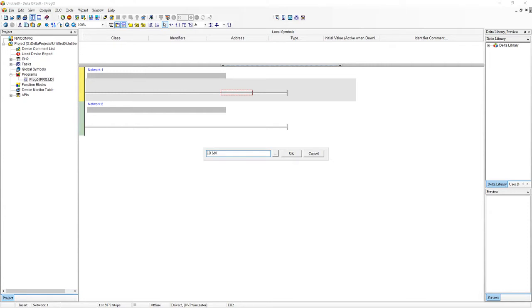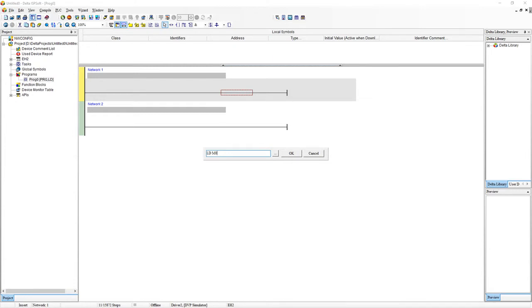So LD is just basically a function which allows us to get an input and when it is turned on it will allow the rest of the rung to execute. So for the conventional programmers this is a lot like an if statement and M0 is like a boolean. And for our electrical guys this is like a switch where we push a button and it energizes and it allows current to flow.